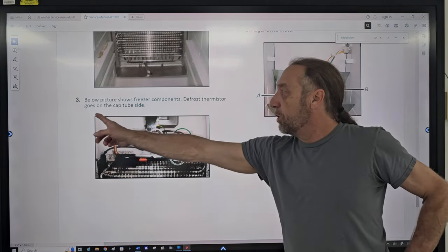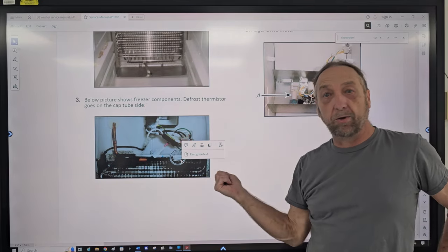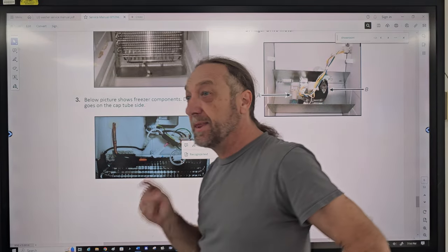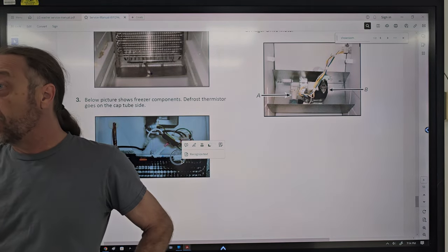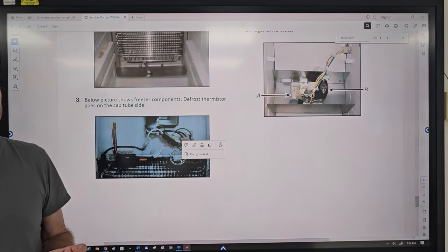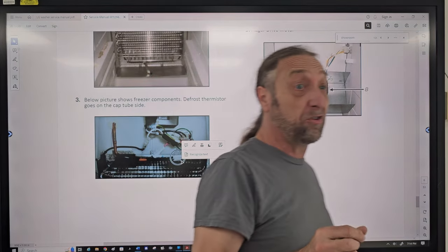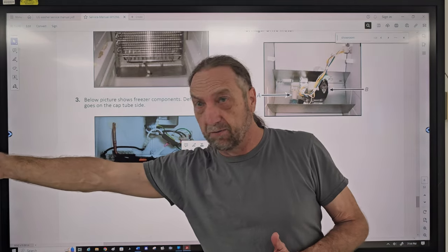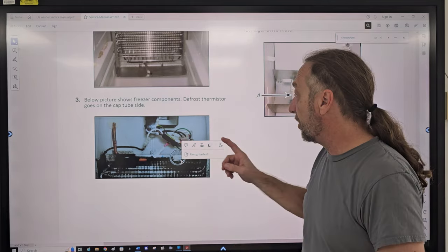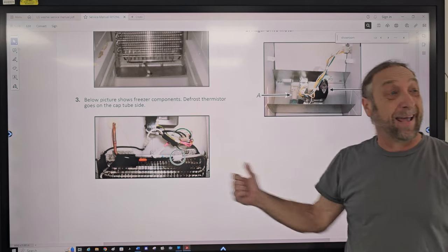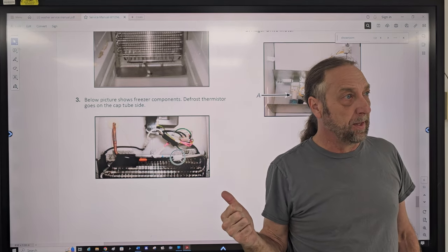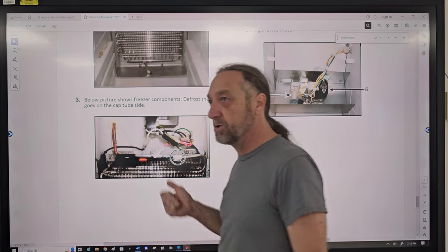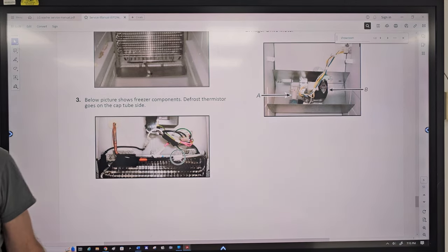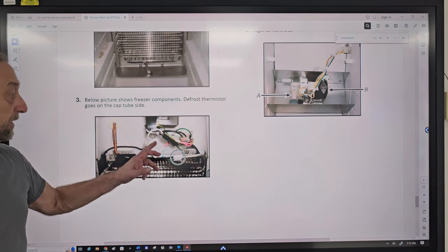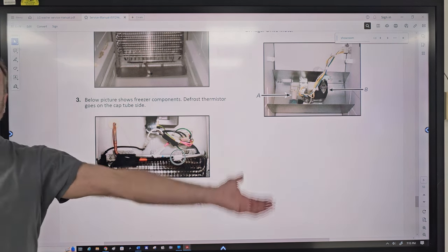The defrost thermistor goes on the cap tube side, where the capillary tube is coming in. It's important they tell you that because normally with a defrost thermostat or bimetal, it's the same idea, they just call it something different. It's located on the suction line, which is the freon leaving the evaporator. But the thermistor is on the freon entering the evaporator at the cap tube. It's measuring the temperature of the refrigerant and how long it takes to pull that evaporator temperature down. It's located on the cap tube, so don't confuse it with the defrost thermostat.